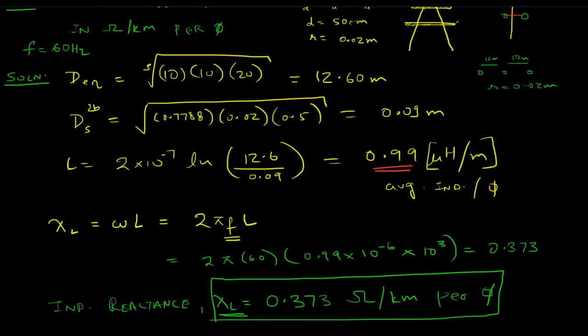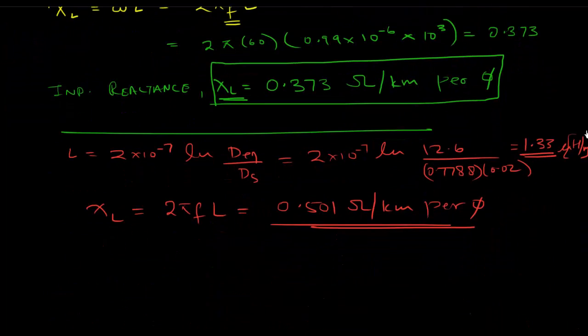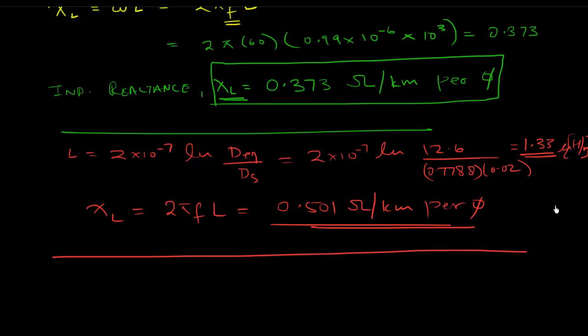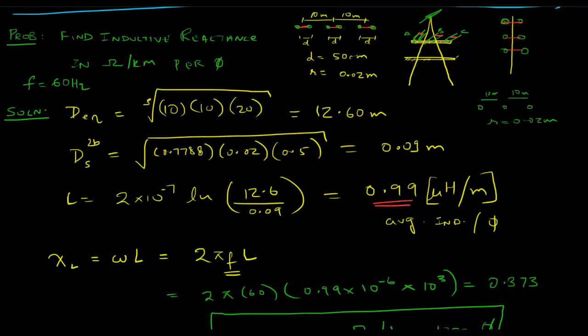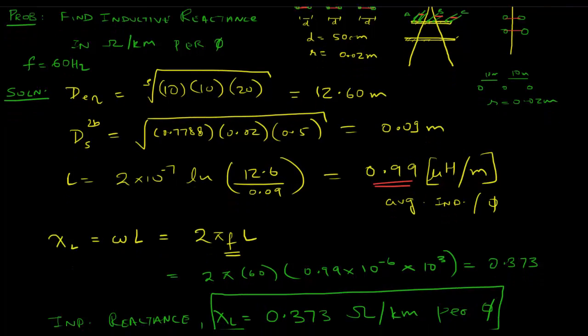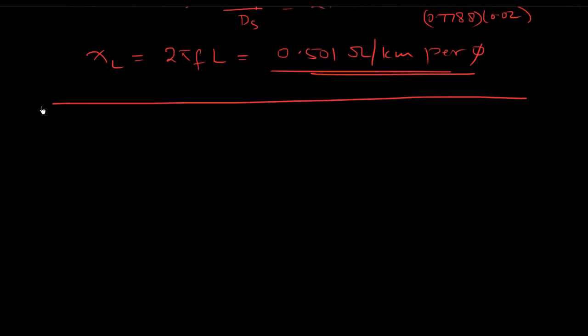Again, you see how we've reduced the XL, the inductive reactance, and the inductance itself by using a bundle situation, by using bundled conductors. That is, as I mentioned in the last video, the biggest advantage of using bundled conductors, apart from the fact that they reduce the corona effect for extra high voltage lines like 200, 230 kV, 400 kV, 500 kV.